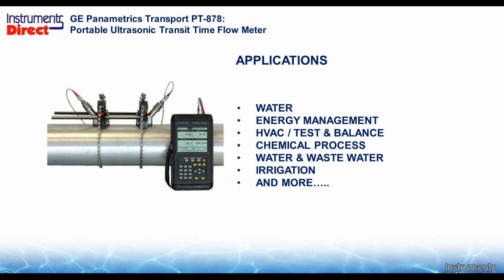And what do we define as a clean liquid application? So generically, ultrasonic transit time flow meters need no suspended solids. They're using time. So ultra pure liquids, jet fuel, deionized water, DI water, water, chill water, hot water, sewage, and that's the bulk of transit time flow meters, which is 95% of all your applications.